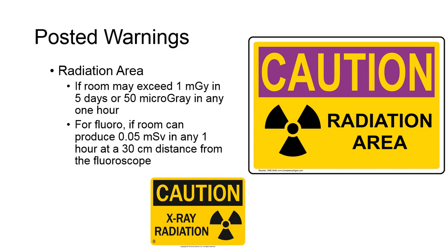Posted Warnings: All radiation warning signs should have the familiar cloverleaf radiation pattern printed against a yellow background. The cloverleaf itself can be red, maroon, or black. A radiation area should have a warning sign displayed if a particular room may ever exceed 1 milligray in 5 days or 50 microgray in any 1 hour. Regarding the use of fluoroscopy, these signs should be observed if the room can produce 0.05 millisieverts in any 1 hour at 30 cm distance from the fluoroscope. A standard sign reading 'Caution Radiation Area' must be posted near all entryways to the room.